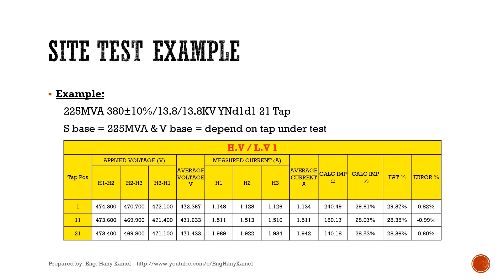Our example: power transformer 225 MVA, 380 with ±10% over 13.8 over 13.8 kV, with vector group YND1D1, and 21 taps. Power base is 225 MVA and voltage base will depend on the tap under test. The results and the calculated errors are shown for the high voltage winding and the first low voltage winding.